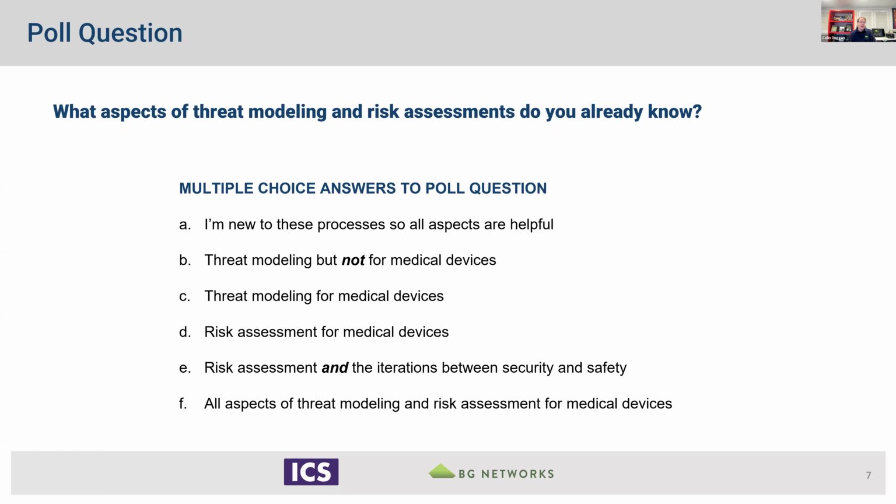You'd want to look at those vulnerabilities, put them back into your threat model and risk assessment to determine if they need to be addressed. You'll do penetration testing. That will find vulnerabilities. You'll come back again. And then the FDA also requires unresolved functional anomalies that may impact security to be analyzed. And that would be another time that you come back to the threat and risk assessment.